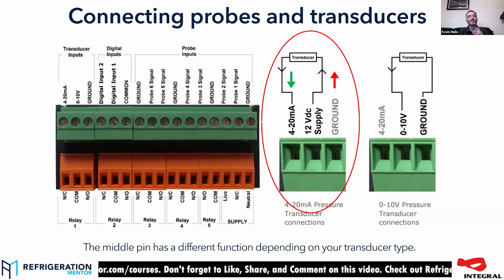Because of that, it doesn't share the transducer directly on that wiring if you've got more than one controller. There are a multitude of ways to share the transducer across the network. And that's how they like you to do it, be that through one of their hubs, where you can connect a transducer and share it to all the things coming out of the network hub, or it can be broadcast over their network from the rack controller, or it can be connected directly. We're going to focus today on it being connected directly, simply because a lot of the same principles apply with setting it up wherever it's connected to.